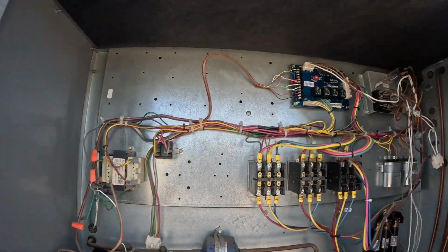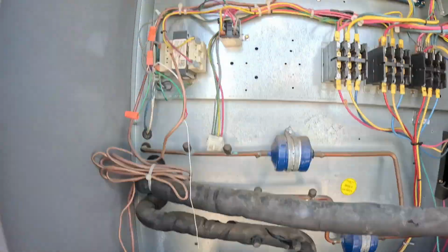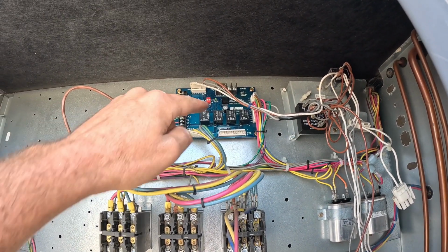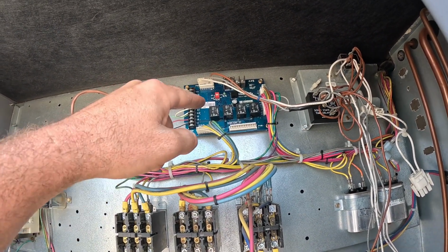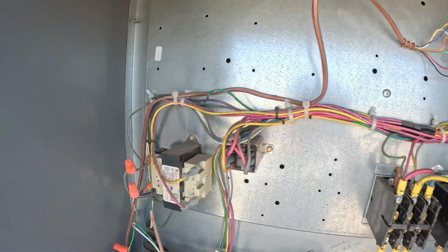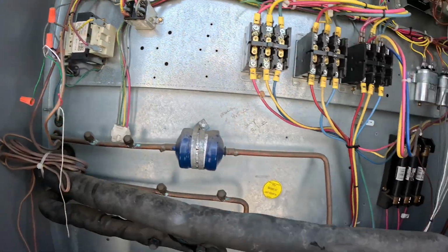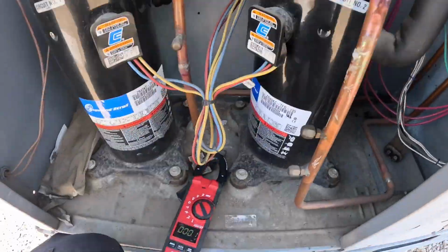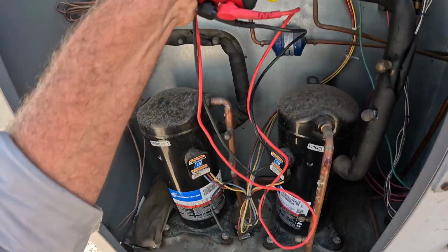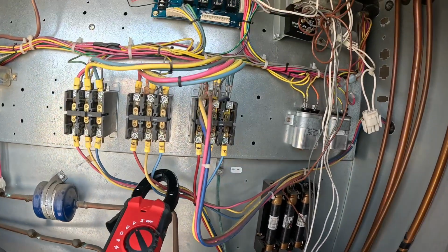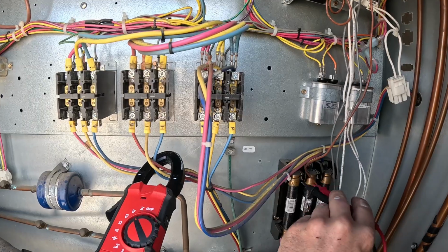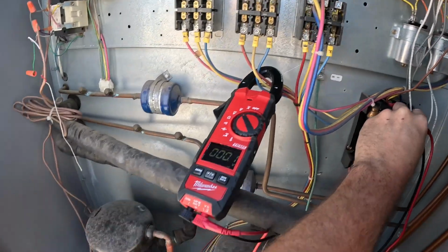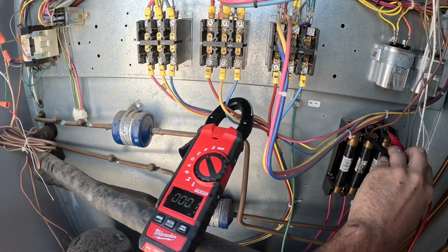First of all, I do a visual inspection. This is inside my control compartment, compressor compartment. I immediately see that I don't have a light on the LED. I don't have an LED light on the board. I can see that my low voltage transformer is not tripped, which immediately makes me believe that we're not having power coming into the unit. So I take my meter, put it on voltage, let's put it up here. I actually bought this so I can work with my hands free. But yeah, you can see we're not having voltage coming into the unit.